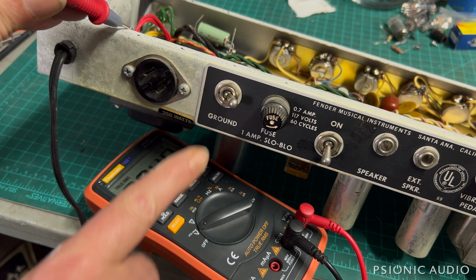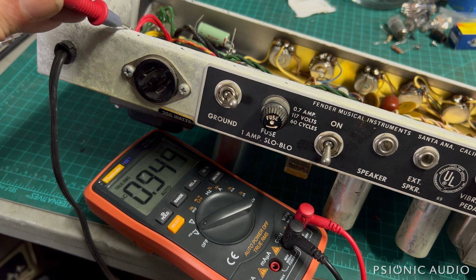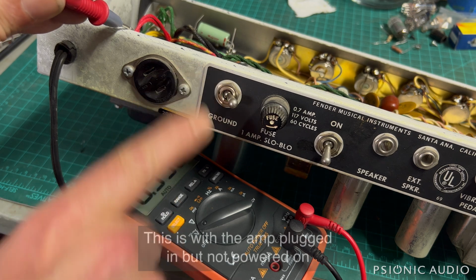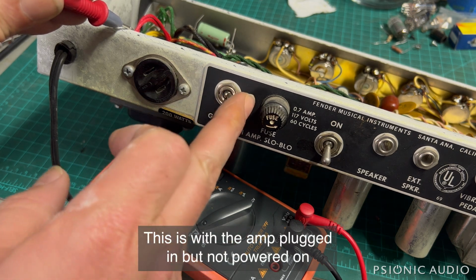With the ground switch in this position, or with the plug in its current location in the receptacle—because the old plugs are not polarized, you can flip them 180 degrees—we've got 0.9 volts between chassis and ground right now. If I flip this the other way...